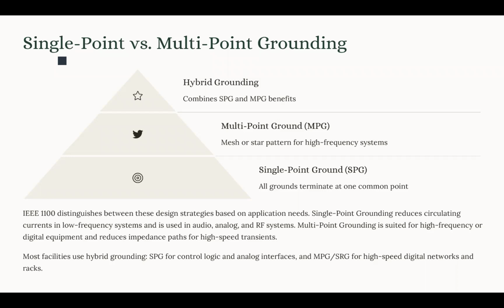When we have high frequency, single point grounding would face a high impedance at those frequencies. A long ground lead basically acts as an inductor at radio frequency and high speed digital frequencies. As you know, the inductor's impedance is jωL. When we have high frequency, we have high impedance, and it creates problems for the sensitive equipment that works with high frequency.